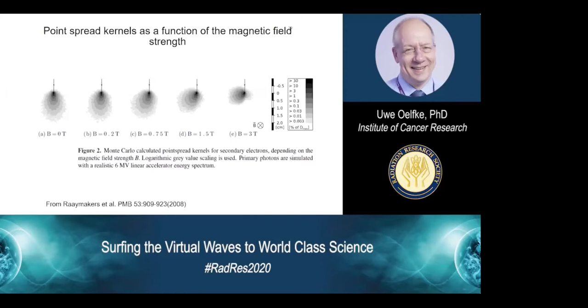Naturally, that doesn't only happen in patients, but also for ionization chambers, where, for instance, the radiation beam can be directed perpendicular to the central axis of the ionization chamber cylinder or parallel, and you can then, for instance, irradiate with the linac. Here's a magnet which is put around the ionization chamber, and you have two configurations like this one, the perpendicular configuration and the parallel configuration, and the signal of your ionization chamber depends on this geometry. And on this slide you can see the different results.